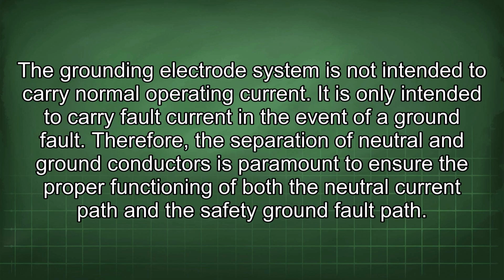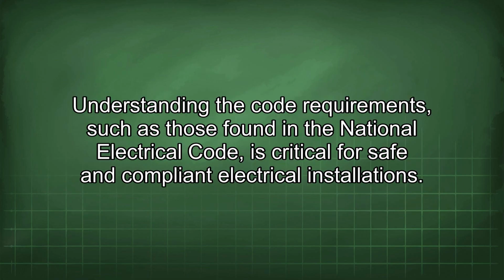The grounding electrode system is not intended to carry normal operating current. It is only intended to carry fault current in the event of a ground fault. Therefore, the separation of neutral and ground conductors is paramount to ensure the proper functioning of both the neutral current path and the safety ground fault path. Understanding the code requirements, such as those found in the National Electrical Code, is critical for safe and compliant electrical installations.